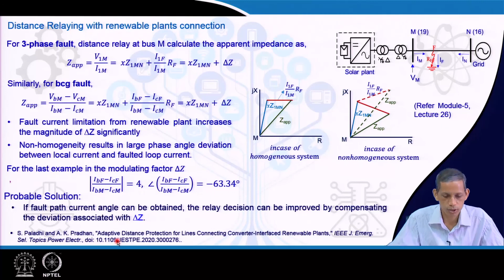Overall, we see that renewable resource plants are generally integrated with an inverter interface, and they modulate the voltage and current signals differently during fault as compared to the synchronous machine based approach. The angle of the equivalent impedance of the plant is much different than that of the synchronous machine or the transmission system. This is a current source, not a voltage source as we take for the synchronous machine based approach, with no negative sequence current.